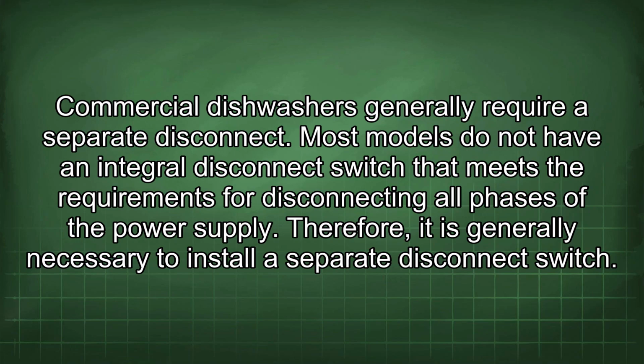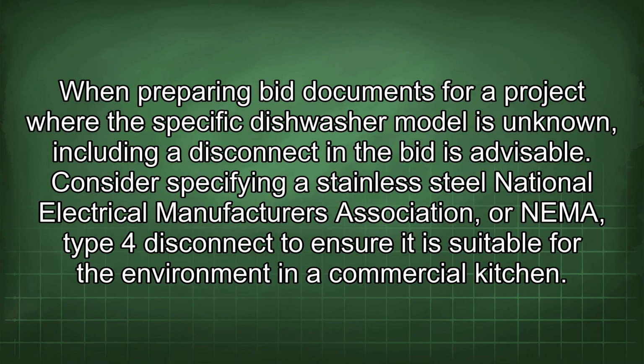Commercial dishwashers generally require a separate disconnect. Most models do not have an integral disconnect switch that meets the requirements for disconnecting all phases of the power supply. Therefore, it is generally necessary to install a separate disconnect switch. When preparing bid documents for a project where the specific dishwasher model is unknown, including a disconnect in the bid is advisable. Consider specifying a stainless steel National Electrical Manufacturers Association, or NEMA, Type 4 disconnect to ensure it is suitable for the environment in a commercial kitchen.